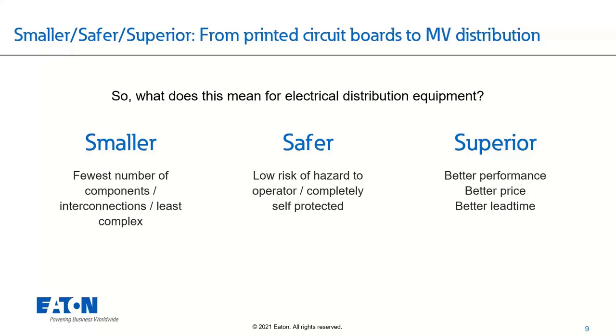So ultimately, what does this mean for electrical distribution equipment in the MV and the LV world? This is really where I derive my smaller, safer, superior commentary here. The smaller is really looking to eliminate unnecessary redundancy, and I'm not referring to a double-ended substation type of redundancy. That's more of an obvious backup scenario, but things like multiple current sensors or multiple voltage sensors, when you're having overlapping zones of protection, you want to make sure that is as seamless and easily coordinated as possible, and ultimately that's going to mean the fewest number of components without sacrificing your redundancy to a certain degree, but without overlapping or overdoing those protection zones as an example.